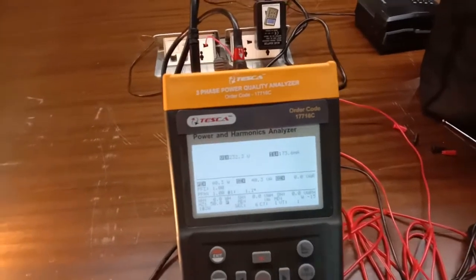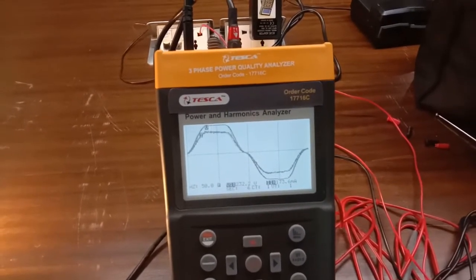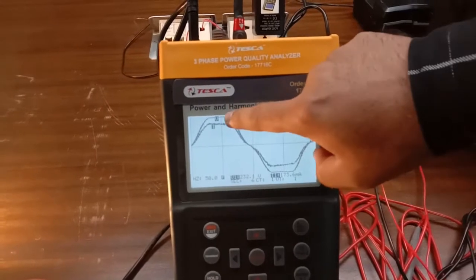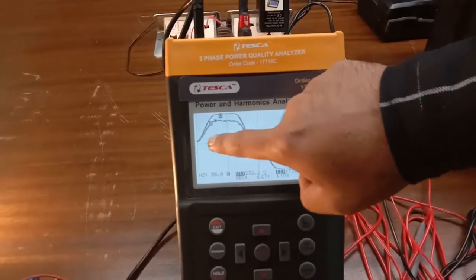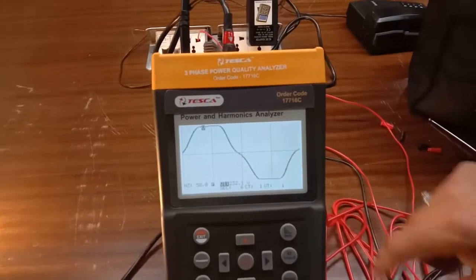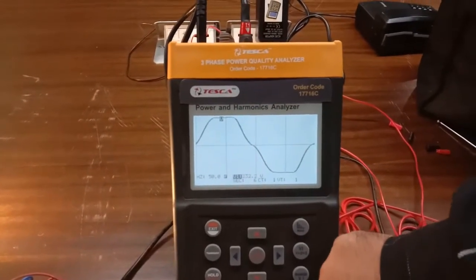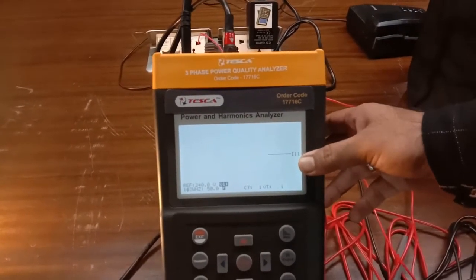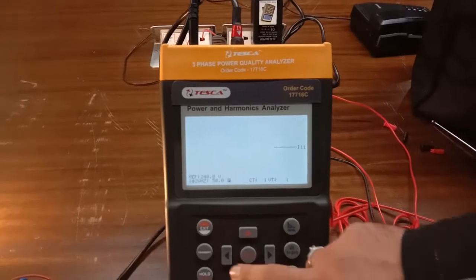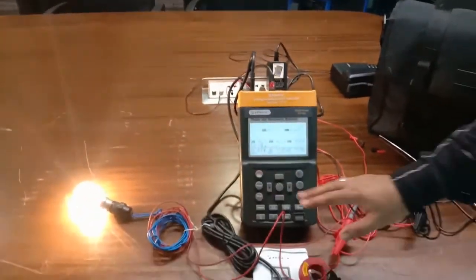Going back to power mode, we now show the voltage and current waveforms. The upper waveform is the voltage (V) and the lower is the current (I) waveform. Using the voltage-only button, the voltage level shows 232.2 volts at 50 Hz frequency. We can then view the phasor diagram — the current phasor with reference to the voltage — and that is how we measure all the parameters of this single-phase system.